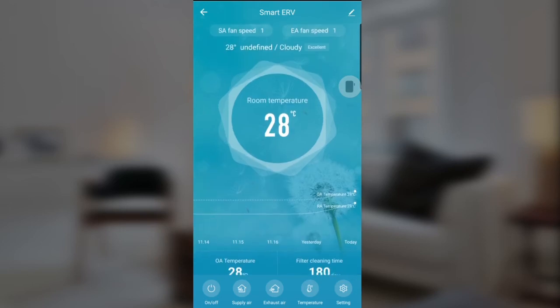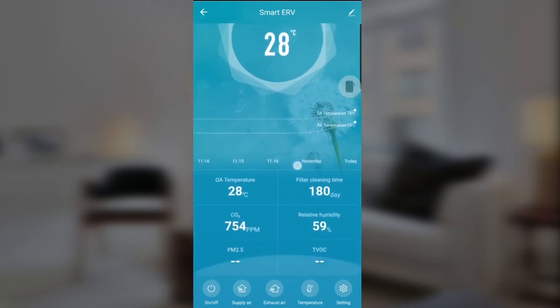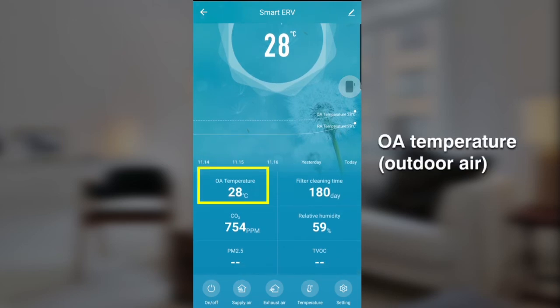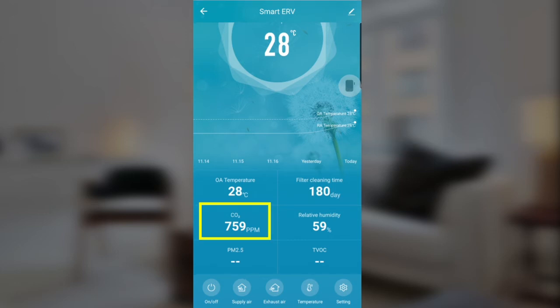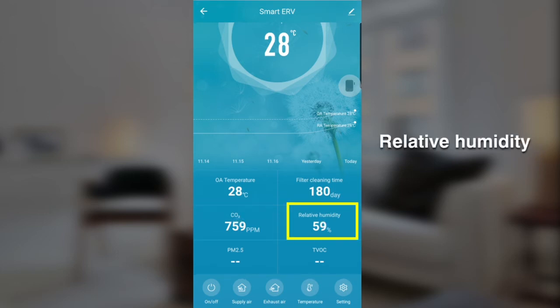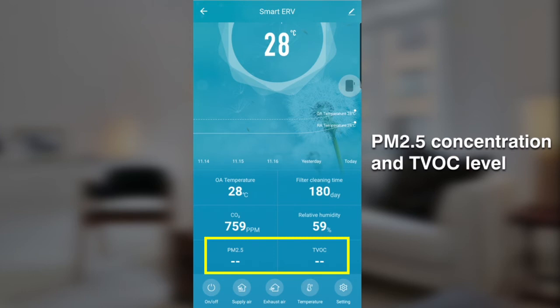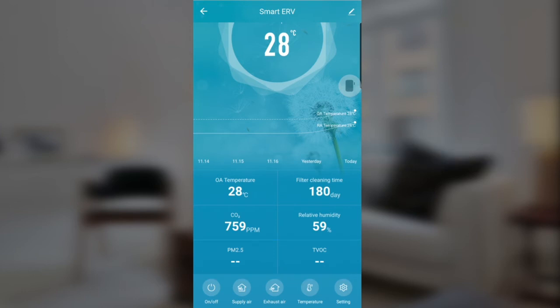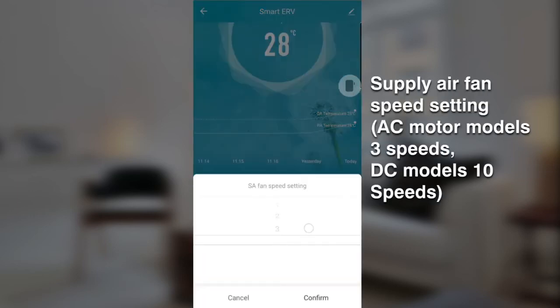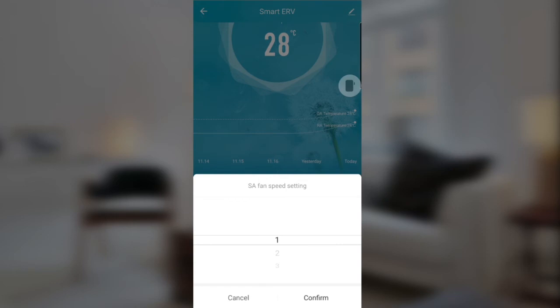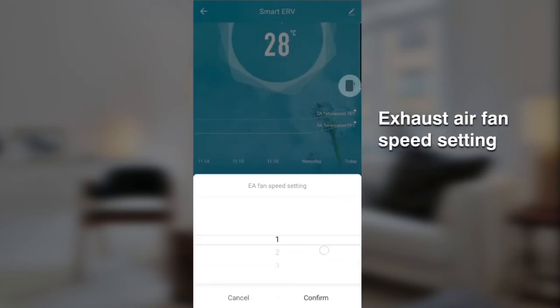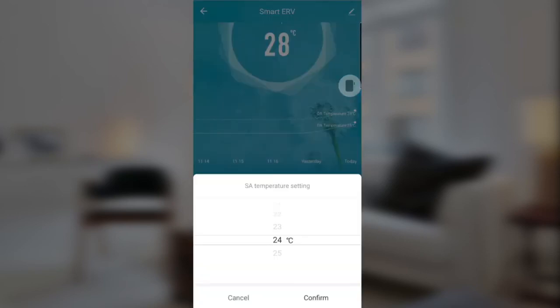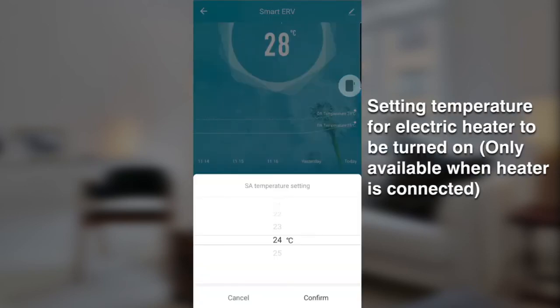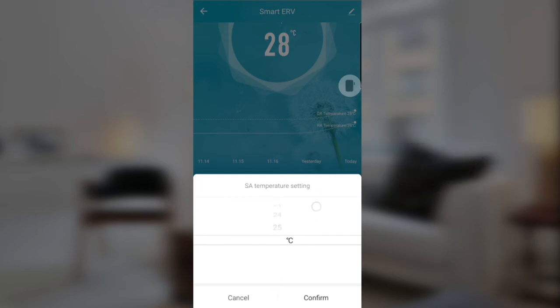Now you should see the fan speed up top and the logo, weather, room temperature. Now at the bottom here you can see the OA temperature and filter cleaning time, CO2 concentration, humidity, PM2.5 concentration, and TVOC level. Now at the bottom bar you can see supply air. Supply air means supply air fan speed. You can change the fan speed, and same for exhaust air. Temperature is for the temperature setting of the electric heaters.